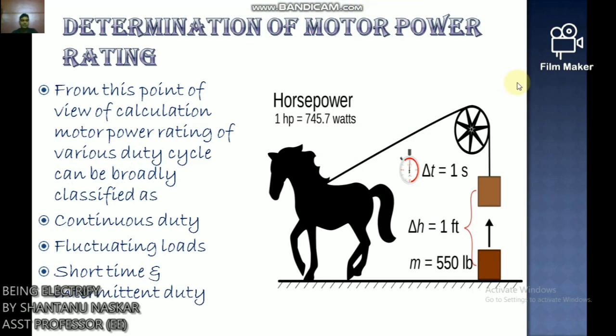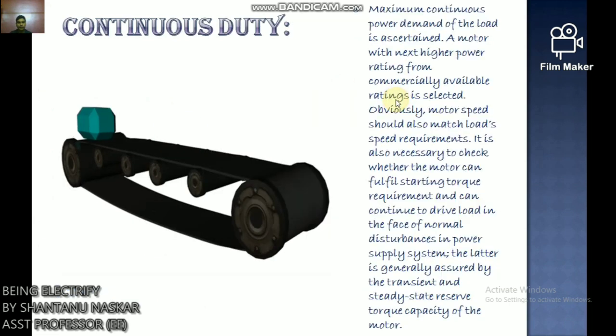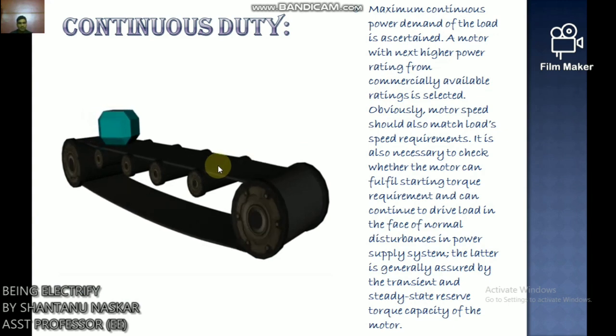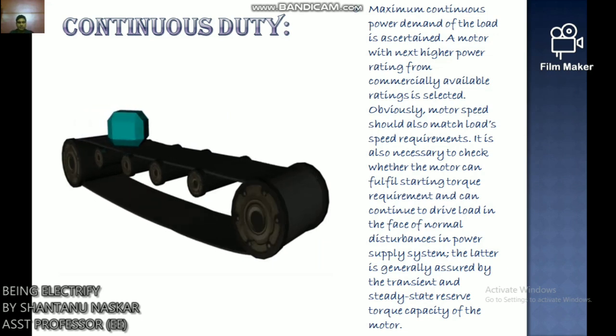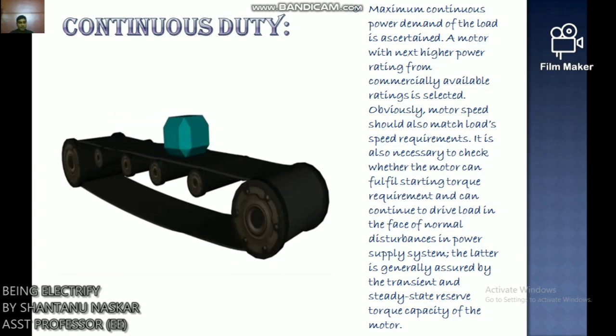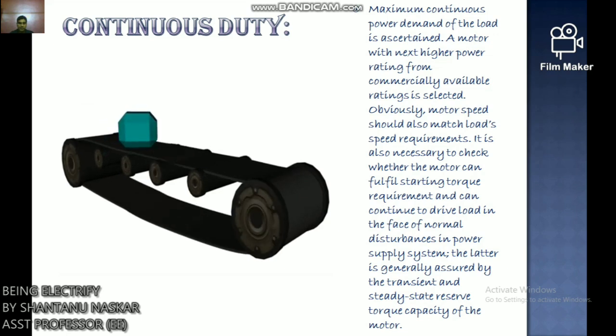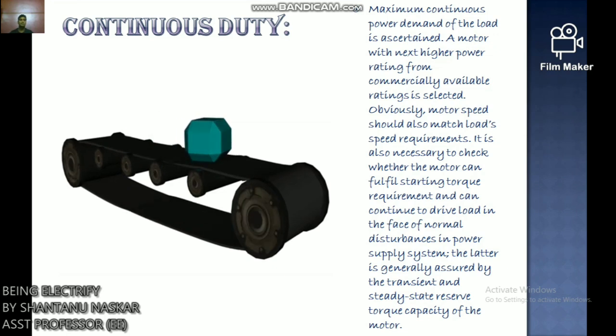Now we discuss determination of motor power rating. For various duty cycles, ratings can be broadly classified as: continuous duty, fluctuating load, and short time intermittent duty. For continuous duty, the maximum continuous power demand of the load is found and the next higher commercially available power rating motor is selected. Motor speed must match load speed, and it must fulfill starting torque requirements and withstand normal disturbances in power supply, ensured by transient and steady state reserve torque capacity.